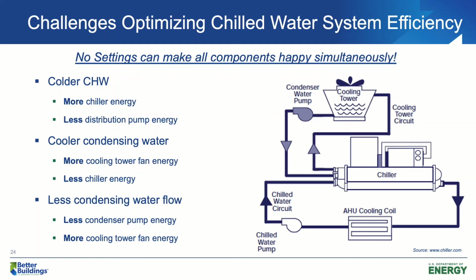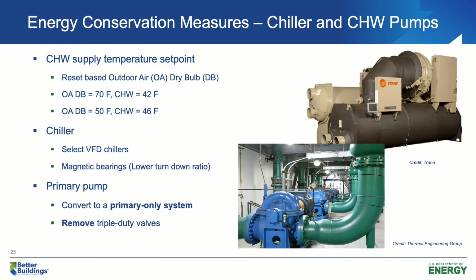How about less condensing water flow? Less condensing water flow definitely will give us some pump energy savings. But on the other hand, the cooling tower fans might need to work harder to achieve the same condensing water temperature. So you can see there are a lot of trade-offs going on the water side. If you really want to optimize the energy performance of the whole system, we might need to perform very complex, very sophisticated simulation work. Luckily, we have some simple energy conservation measures to help you to achieve near optimum energy performance. For example, we can reset chilled water supply temperature set point based on outdoor air temperature.